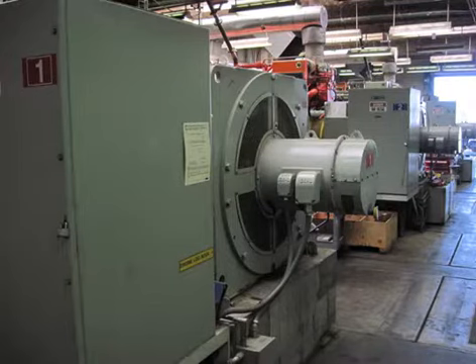The cogeneration plant is powered by the methane gas that is produced in the digester tanks and produces electricity for the rest of the treatment plant operations. The digester tank methane supplies a full 1/6 of the fuel needed for the plant generators, which power everything from the lighting to the air and water circulation pumps.